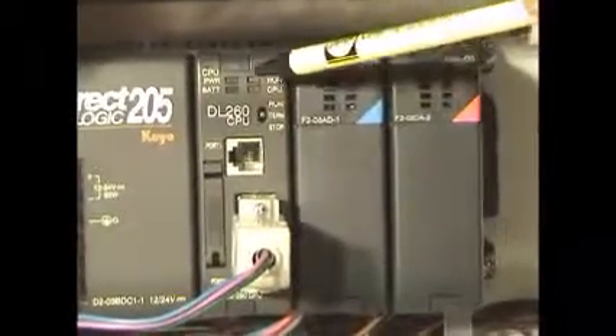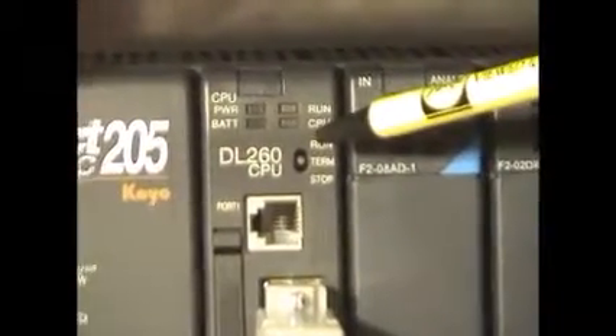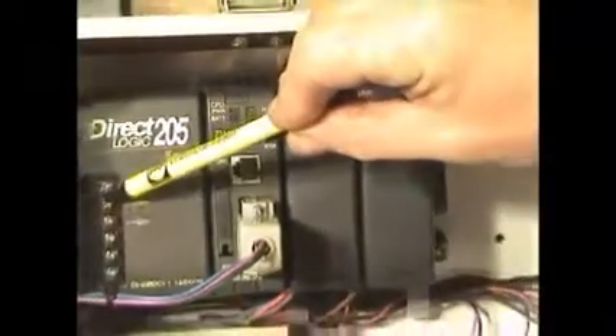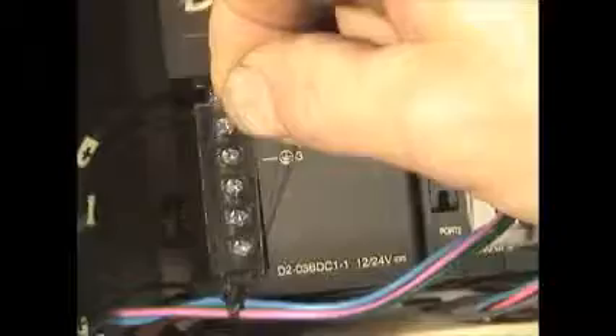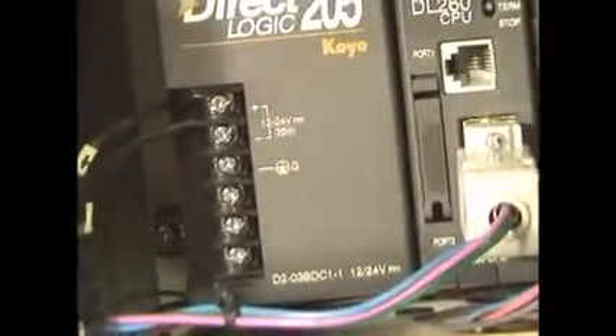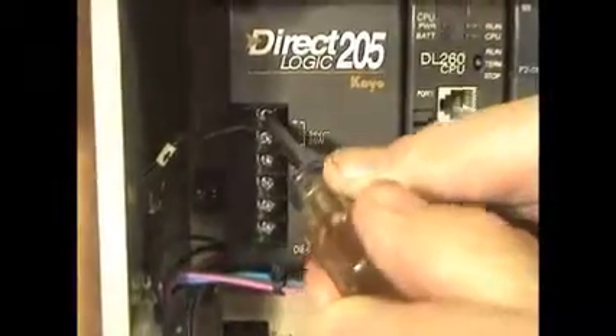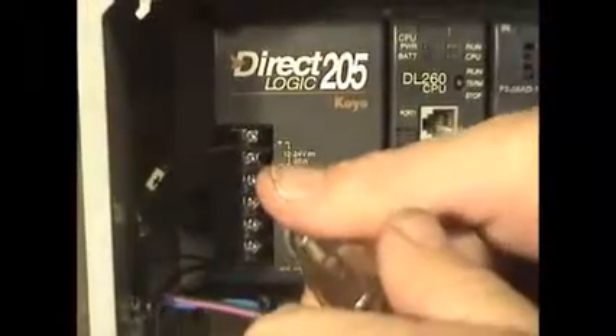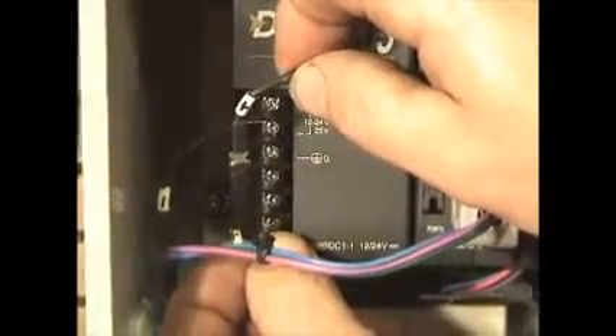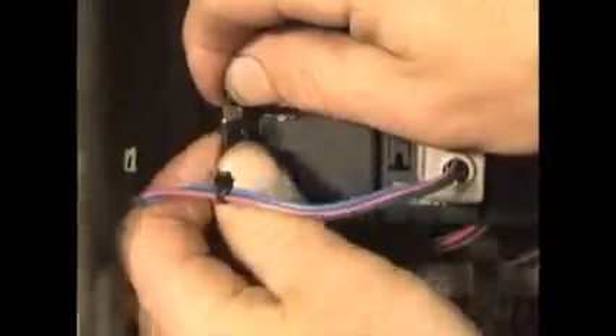If the PLC CPU light and run lights are not illuminated when there is power to the rest of the Dredgemaster system, there may be a failed diode. To check the diode, remove the front cover of the power supply. Next, you'll need to loosen the two screws holding the diodes. Next, remove the diode from the electrical connector by simply pulling it apart.